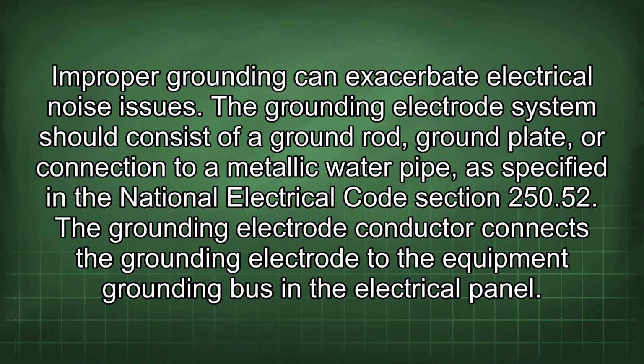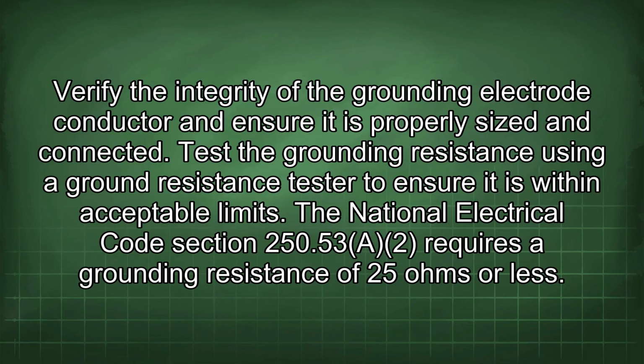The grounding electrode system should consist of a ground rod, ground plate, or connection to a metallic water pipe, as specified in the National Electrical Code Section 250.52. The grounding electrode conductor connects the grounding electrode to the equipment grounding bus in the electrical panel. Verify the integrity of the grounding electrode conductor and ensure it is properly sized and connected.